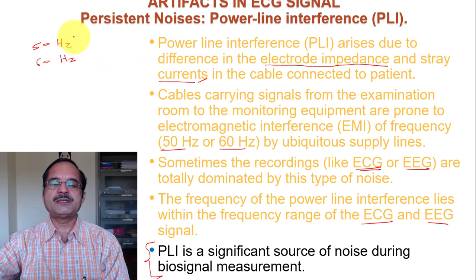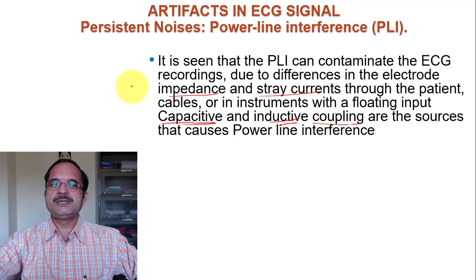Power line interference can contaminate ECG recordings due to differences in electrode impedance and stray currents, which we already discussed, through the patient cables or instruments with floating inputs, and capacitive and inductive coupling. Capacitive and inductive couplings are again sources of power line interference, because capacitance and inductance pass AC frequency. So 50 Hz and 60 Hz will easily pass through the capacitive and inductive coupling, and because of that it will generate power line interference on ECG and EEG recordings.